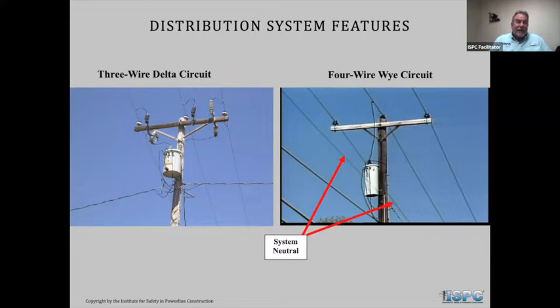3-phase delta circuit. All right. On the left-hand side, you can see we still have our 3 conductors up top, but what's missing is the system neutral. So a delta system does not have a system neutral. Therefore, any return current will go down every transformer, every piece of equipment that has a ground wire going down the pole. That return current is going back through the earth. So, the question again, why don't we get shocked? Because if we have everything grounded, we have collapsed any voltage that may be on the line.